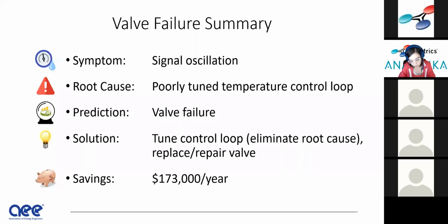In a preventative maintenance program or any other maintenance program, if this happened, you might repair the valve and move on, right? Oh, the valve blew, let's put in a new one. But if the tuning hasn't been addressed, you're still going to have that oscillation, and you're going to have failure in another few years or potentially sooner. So root cause is very important. And here the savings were $173,000 a year.